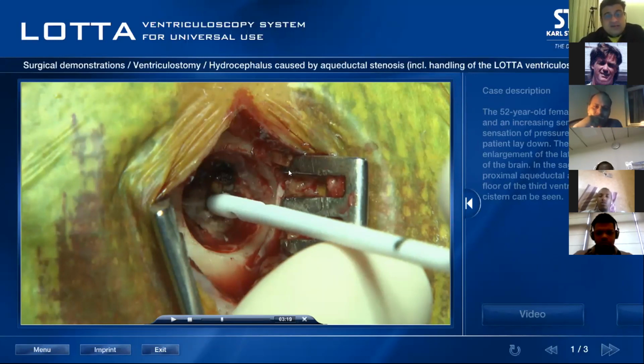Number two, while a surgeon is making a burr hole, the paramedical staff can help in connecting the camera, the light cable, the cautery cable, and doing a white balance, and save 10 minutes of anesthesia time. It is important to also connect the endoscopic monopolar and bipolar electrodes with cautery, because in a standard ETV, you may not use a bipolar electrode, but God forbid, if there is an emergency or something, if cables are not connected, it can lead to a disastrous condition, because in neuroendoscopy, we say it is a highly precision surgery.